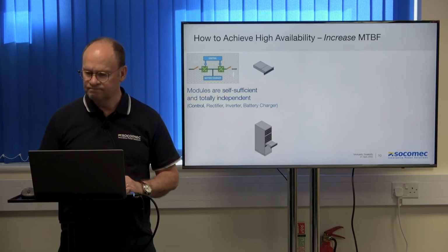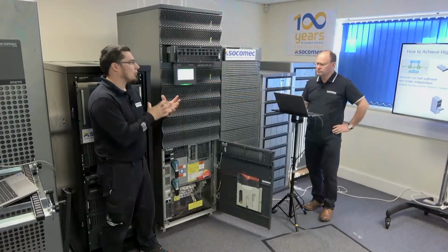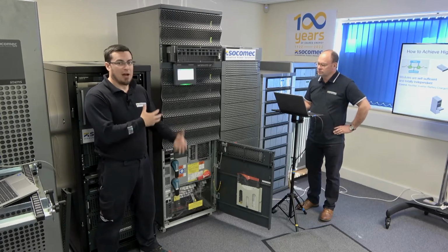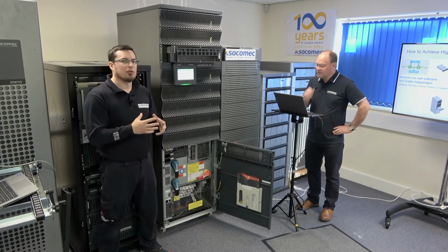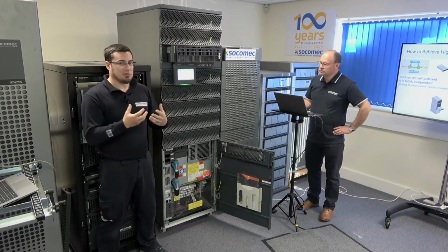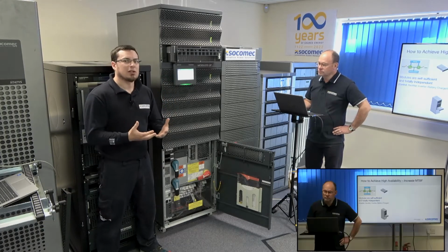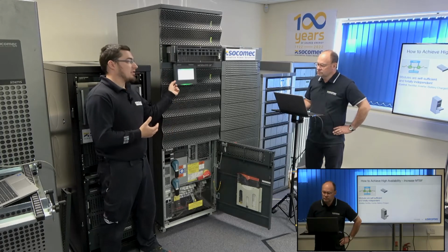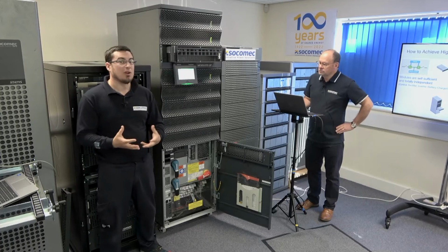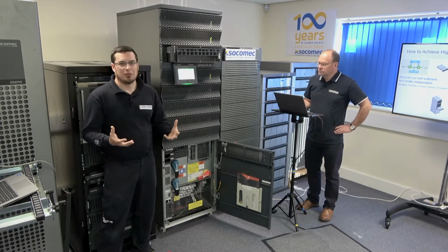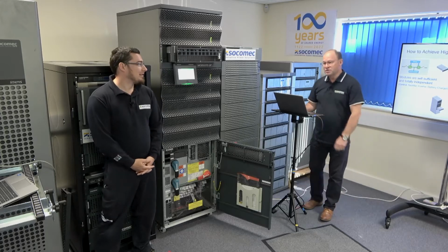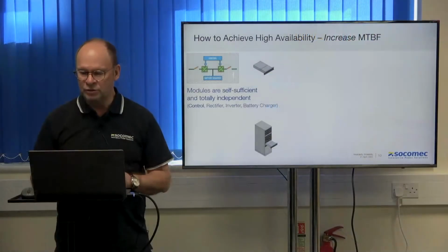And as David mentioned there, the controls are all independent, so even if the main control board failed or any of the power supplies failed, the system still carries on running. The modules are intelligent. They've got their own software in them that says if this happens you carry on running no matter what. So like David said, the displays are all hot swappable, everything is hot swappable, absolutely everything, so the system always runs even in a really catastrophic failure, which is pretty unlikely. Yeah, so it's a very robust design and it's a reliable build, which is what we want.